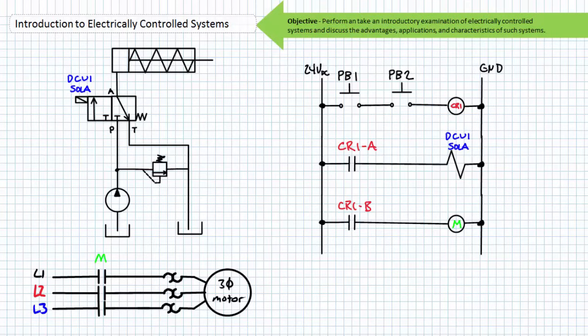Consider an operator simply so tired of keeping both hands on push button 1 and push button 2 while the cylinder extends, and so desperately longing to take a smoke break. The operator takes it upon themselves to attach a low resistance wire in parallel to push button 2, effectively making push button 1 the sole input in charge of extending this cylinder. As if that wasn't enough, the operator takes another jumper wire and bypasses the normally open contact CR1B, effectively keeping the drill constantly spinning.